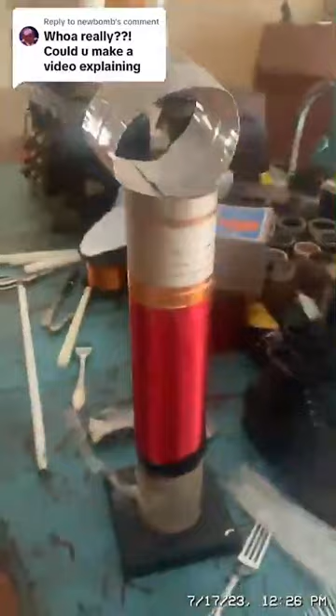Anyway, now I'm going to do my demonstration. I'm going to be setting y'all on this music stand so that it doesn't interfere with my phone. Before I do this demonstration, I would like to tell you what's going on. First, I will touch a metal object to the cauterizing terminal on the diathermy machine, and you will observe that there are only about an inch long sparks. Then, after I do that, I will connect this coil to that cauterizing terminal, the bottom of this coil I wound, which, by the way, is wound to 1/4 of the wavelength of the frequency coming out of this diathermy machine. The frequency on this diathermy machine is about 29 megacycles, so this is 1/4 wavelength of 29 megacycles.